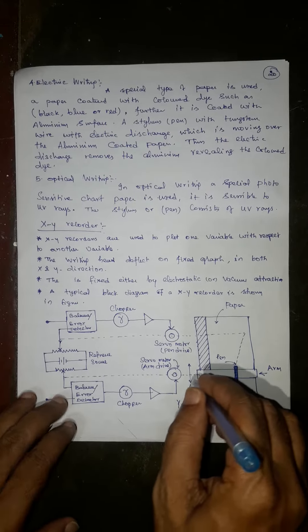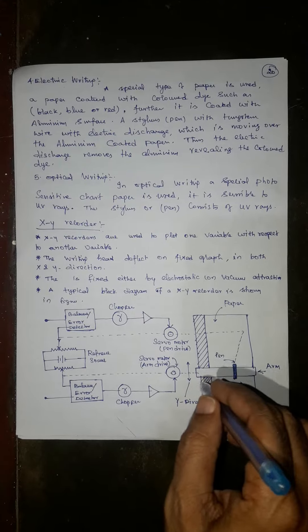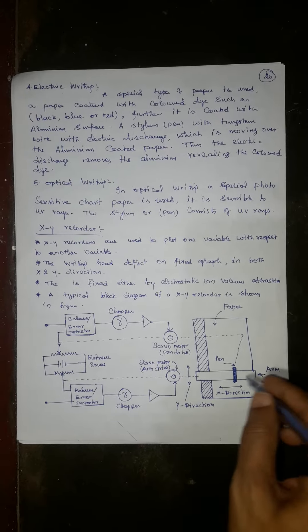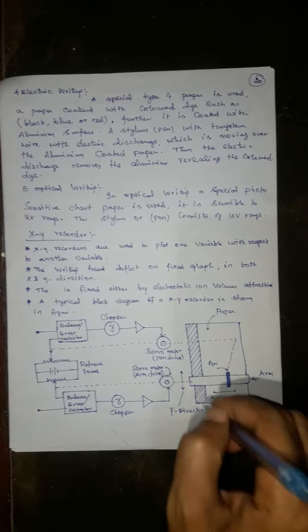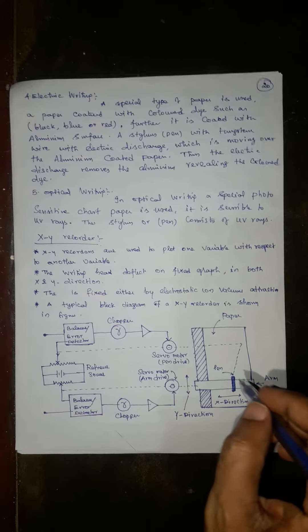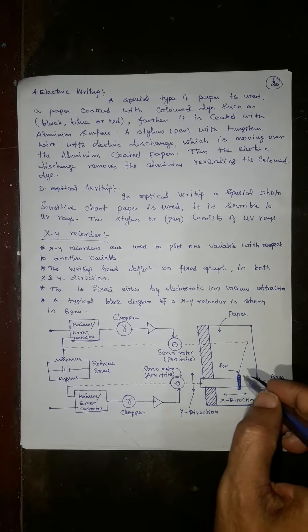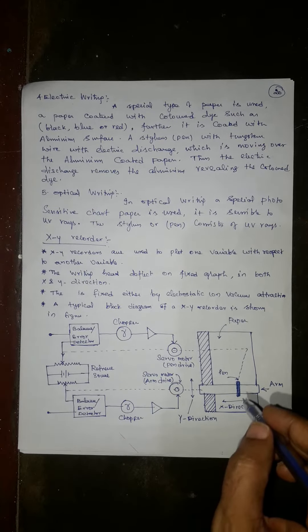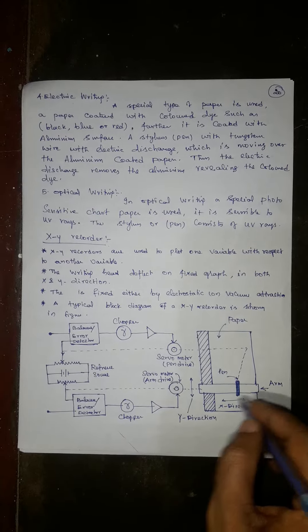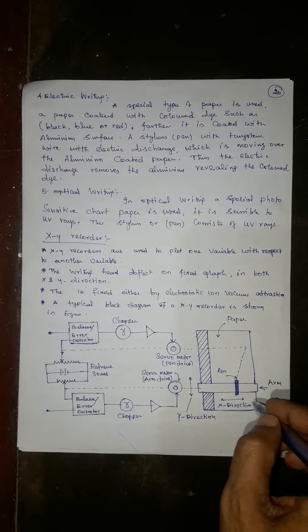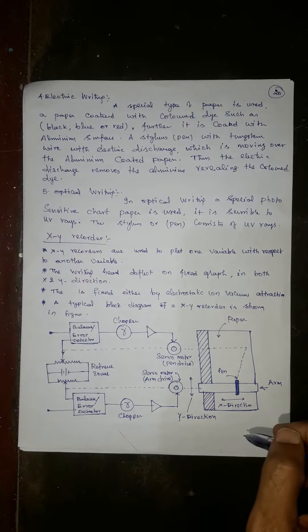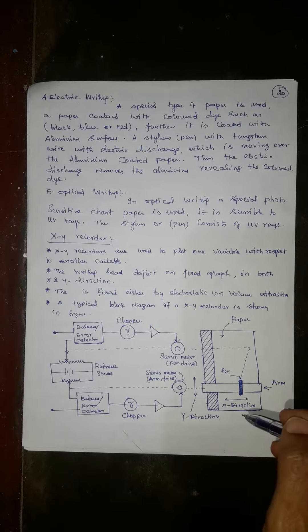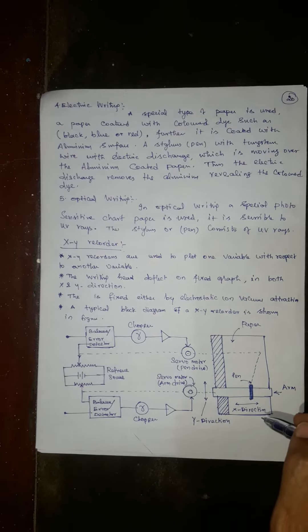That is the basic difference between XY recorders and strip chart recorders. In an XY recorder, the paper is fixed. XY recorders are used to plot one variable with respect to another variable. The writing head deflects on a fixed graph or fixed paper in both X and Y directions. The fixing of the paper or graph is by electrostatic effect or vacuum attraction.